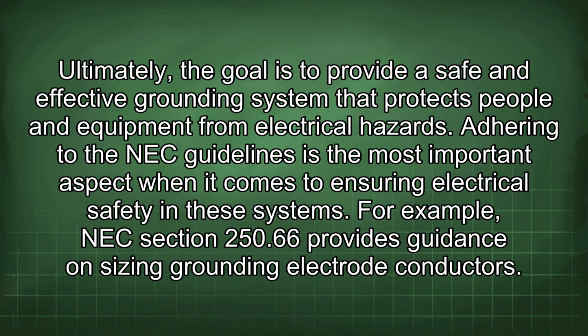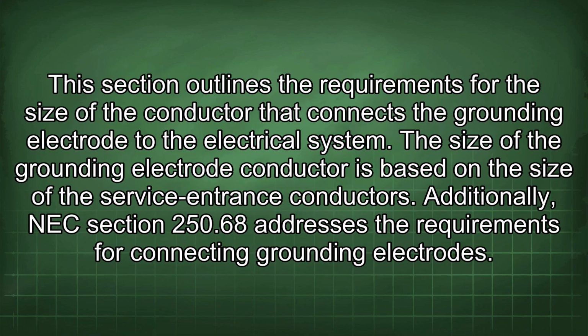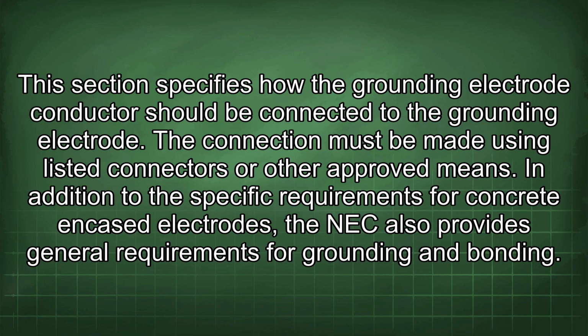For example, NEC Section 250.66 provides guidance on sizing grounding electrode conductors. This section outlines the requirements for the size of the conductor that connects the grounding electrode to the electrical system. The size of the grounding electrode conductor is based on the size of the service entrance conductors. Additionally, NEC Section 250.68 addresses the requirements for connecting grounding electrodes. This section specifies how the grounding electrode conductor should be connected to the grounding electrode. The connection must be made using listed connectors or other approved means.